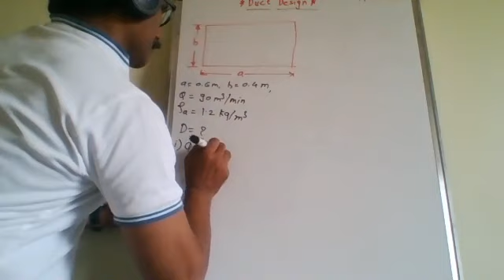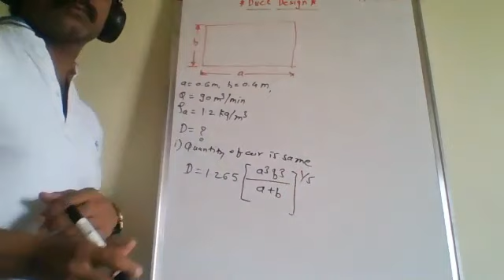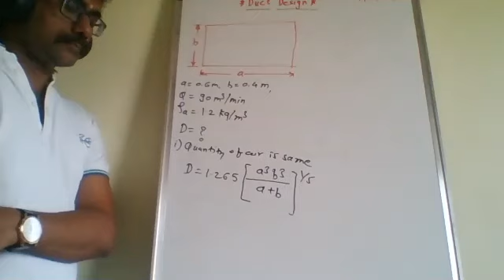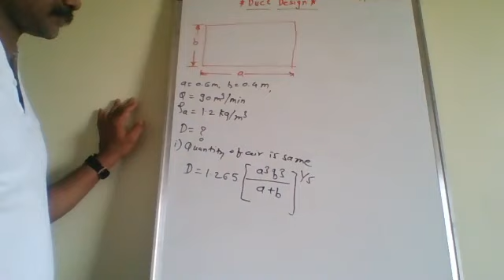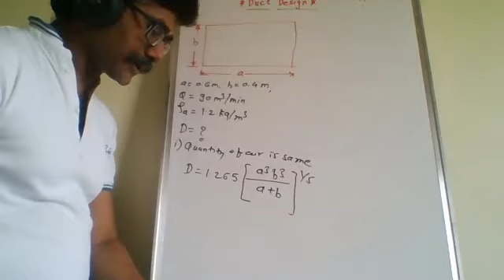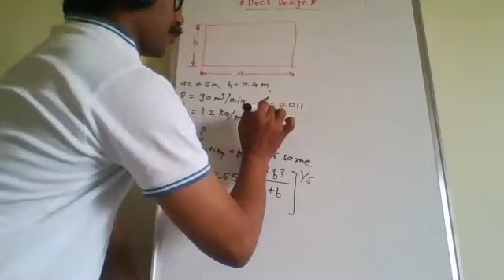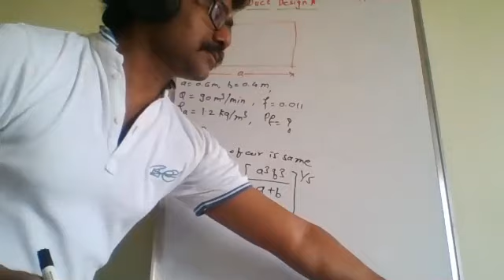Then, as in today's first problem that we saw, the equivalent diameter for this condition is given as 1.265 into the bracket A cube B cube divided by A plus B, bracket raised to 1 by 5. That is the formula we have. Additional information that I forgot here: in the latter part of the problem, it is mentioned that assume friction factor 0.011, and it is also suggested to find out the pressure loss per 100 meter length of the duct. So PF that we have to find out, provided the length is nothing but 100 meter.